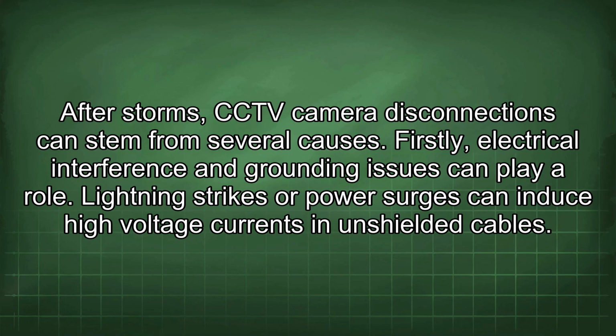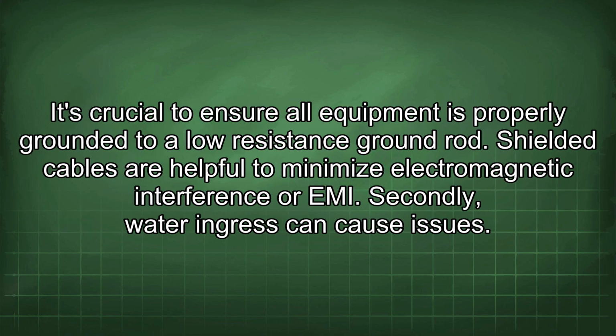After storms, CCTV camera disconnections can stem from several causes. Firstly, electrical interference and grounding issues can play a role. Lightning strikes or power surges can induce high voltage currents in unshielded cables. It's crucial to ensure all equipment is properly grounded to a low resistance ground rod. Shielded cables are helpful to minimize electromagnetic interference, or EMI.